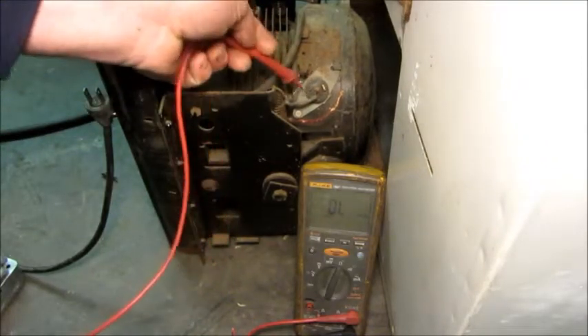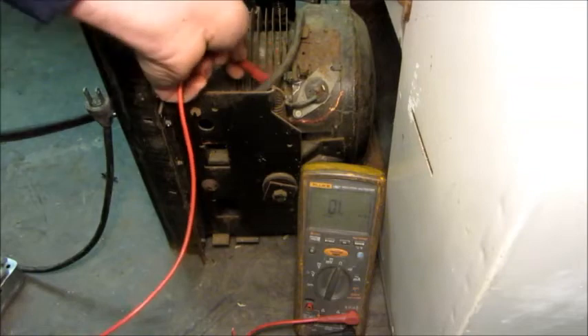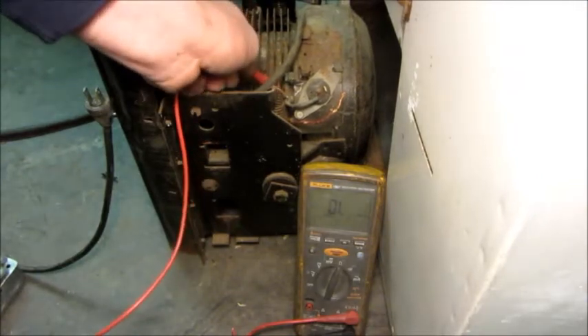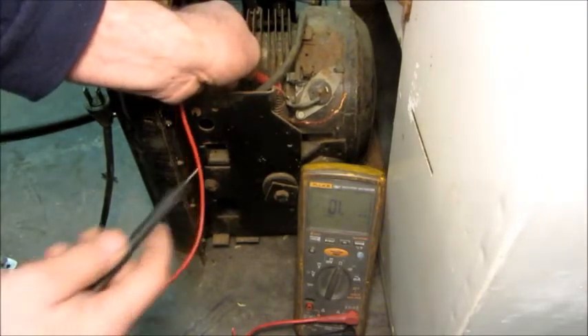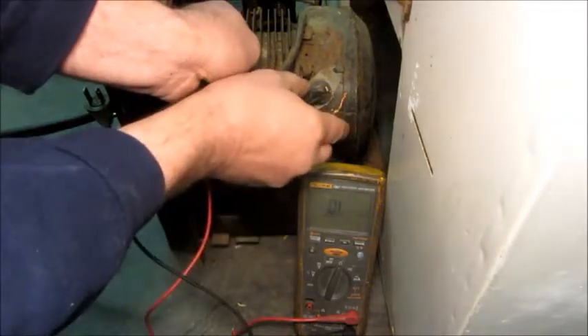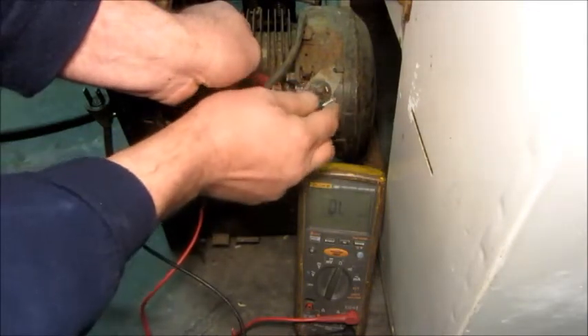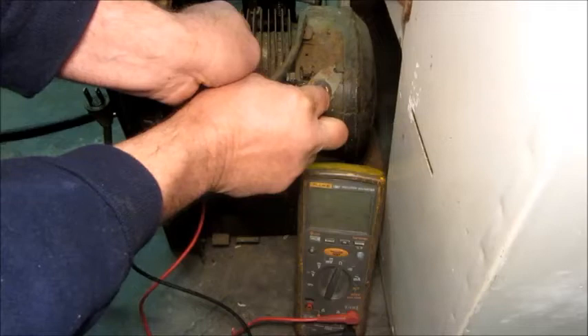Now we know that the common wire goes through the circuit breaker, and that round thing right there, that's obviously a motor overload circuit breaker. So I'm going to take for granted that middle terminal is the common. I'm going to check to this lower wire. Make sure I'm not blocking the view there.